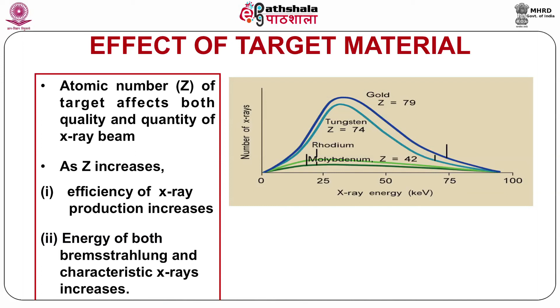First is gold, second is tungsten, third is rhodium and fourth is molybdenum. These targets are of different Z value, so we can observe from here that as the Z value of the target increases, X-ray production efficiency increases. However, if we consider other characteristics of the target material, one has to select an optimum target which satisfies other characteristics of the target, not only the efficiency of production of X-ray. But from this figure we can conclude that gold seems to be one of the best targets, but practically we know that tungsten is one of the most suitable targets for production of X-rays.